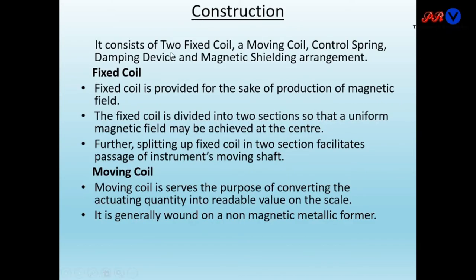The construction consists of two fixed coils, a moving coil, control spring, damping device, and a magnetic shielding arrangement. The fixed coils provide the magnetic field. The fixed coil is divided into two sections so that a uniform magnetic field may be achieved at the center, and splitting into two sections also facilitates passage of the instrument's moving shaft.